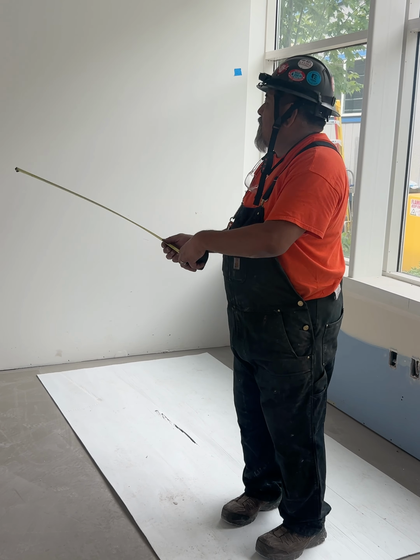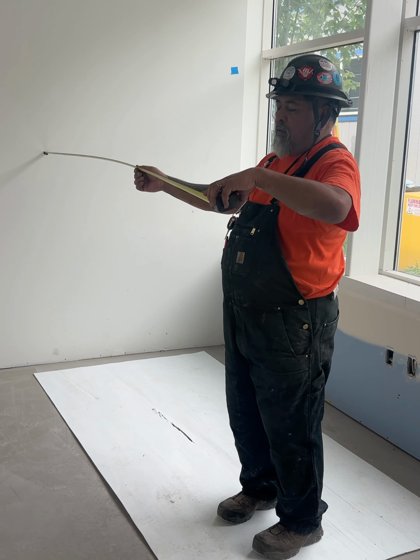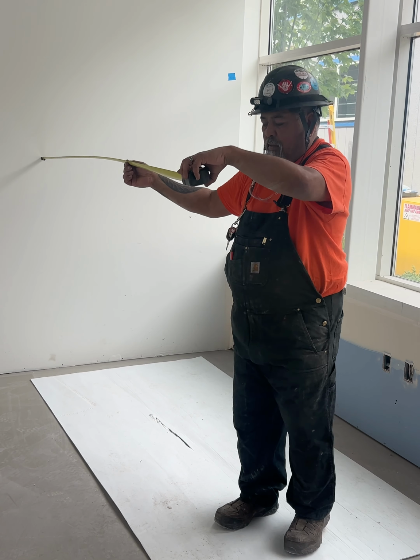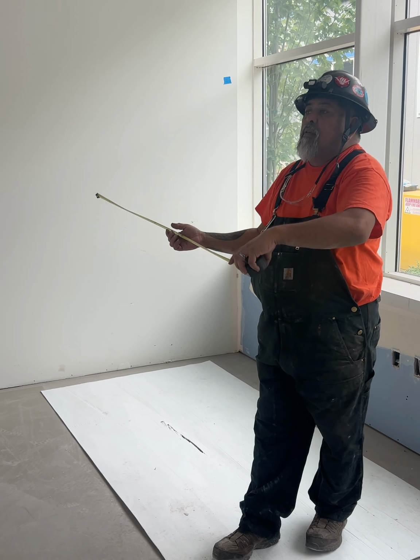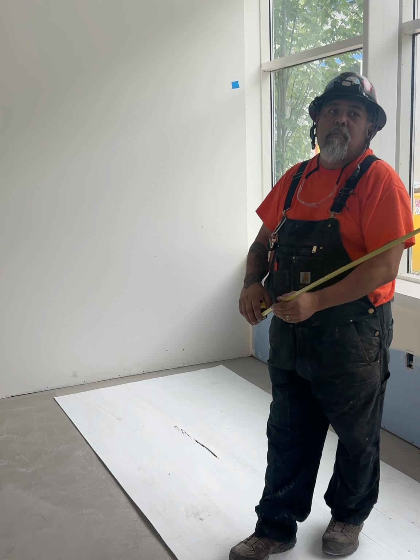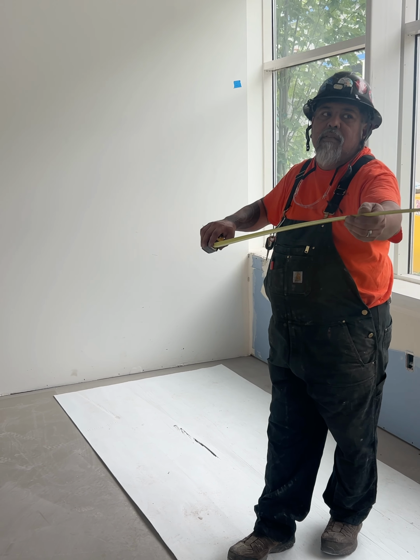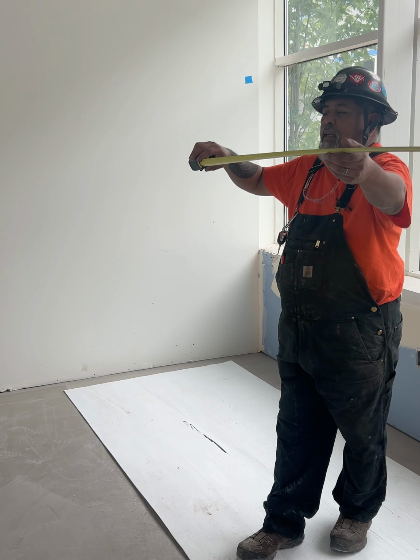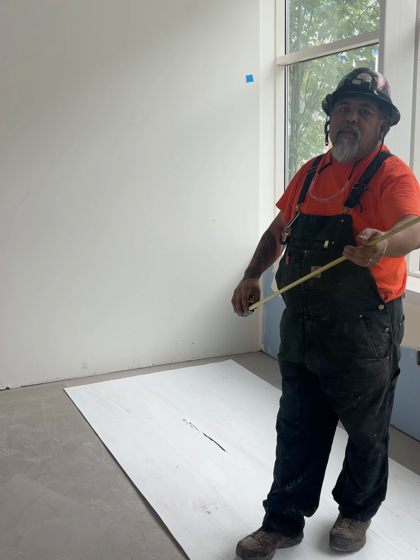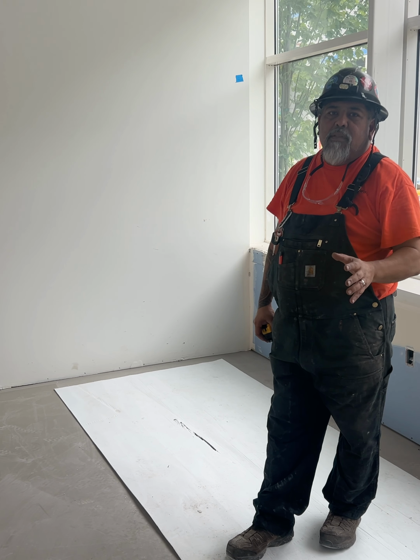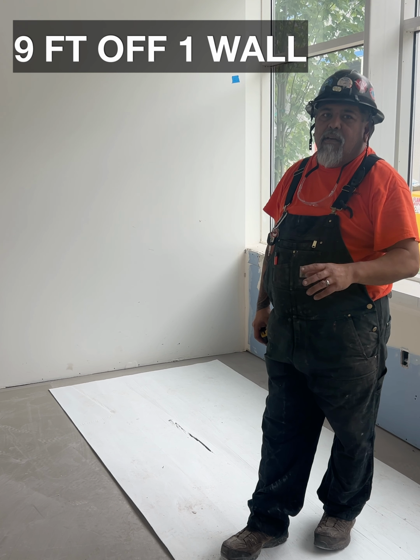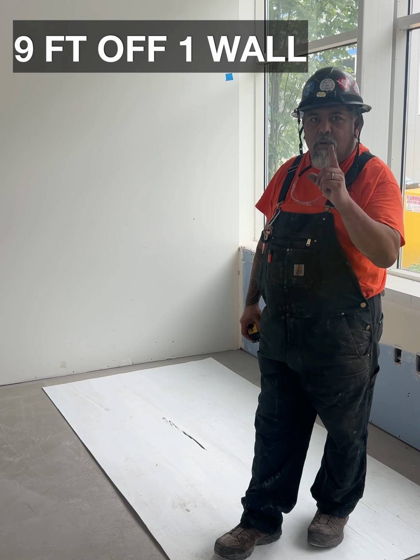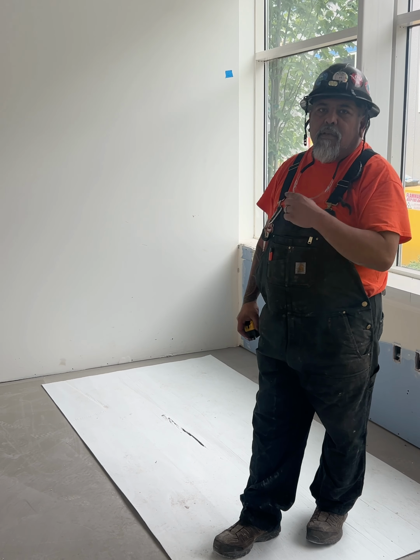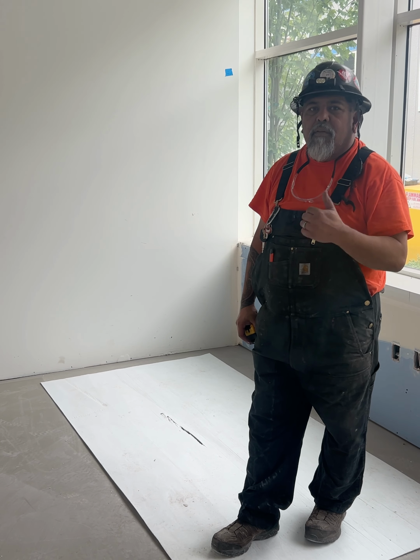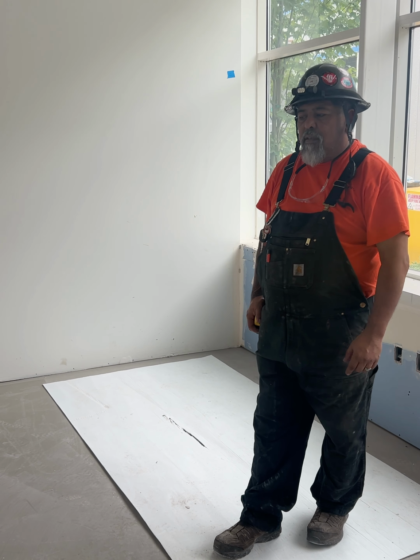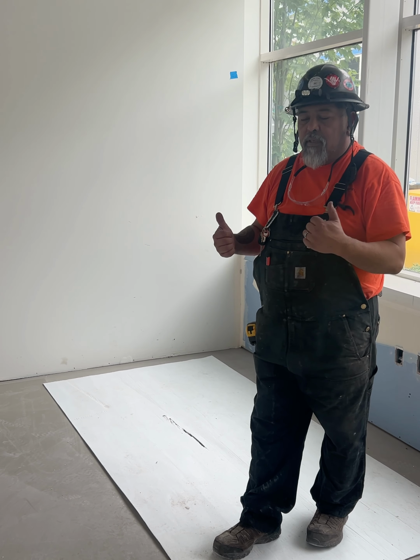If I go 7/6 off this wall, which is right here, then I'm probably going to be over 7/6 on this one, which I am. I'm 8 feet. But the small room rule says you can be 9 feet off that one wall, just one, but you have to make sure you meet 7/6 of the other 3. As long as you apply that, you're good.